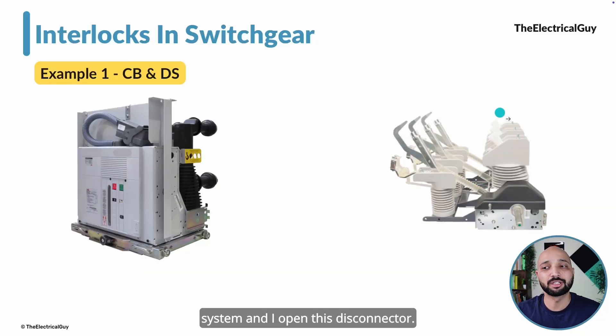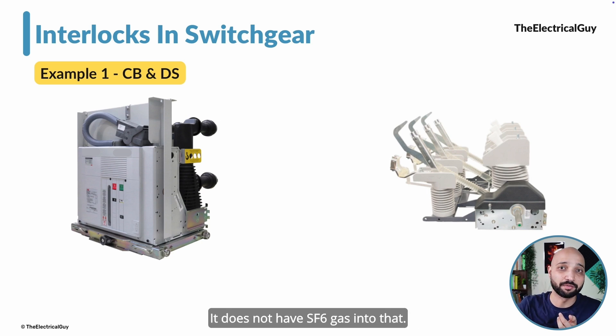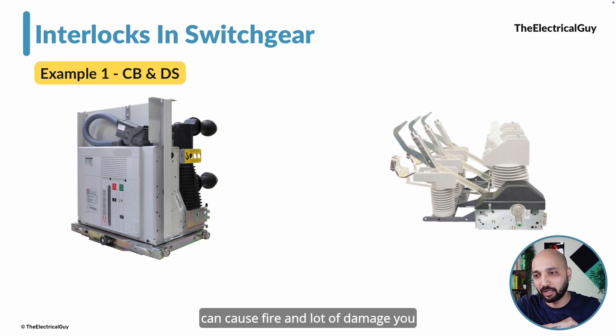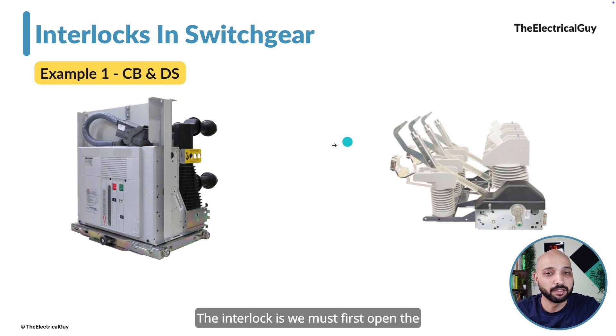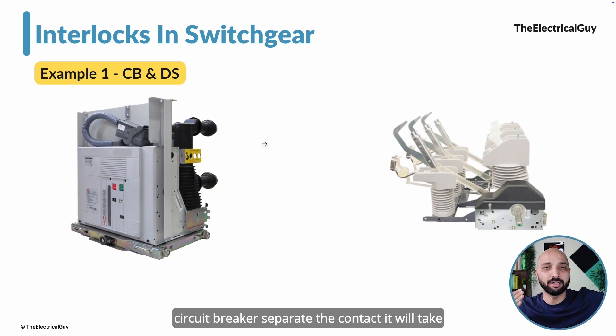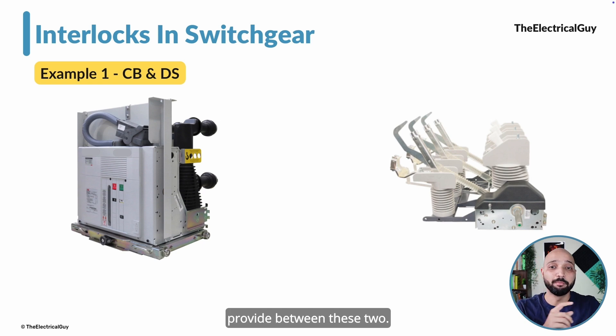If the current is flowing and you open the disconnector, the moment the contacts start separating, an arc will strike — 100 percent. The disconnector has no capability to quench that arc; it has no vacuum interrupters or SF6 gas. That arc can reach an extreme level and cause fire and significant damage. So the interlock is: you must first open the circuit breaker — which will interrupt the current successfully by handling the arc — and only after that open the disconnector. With no current flowing, there is no problem.